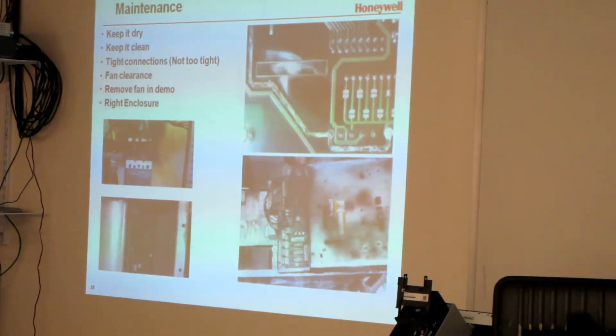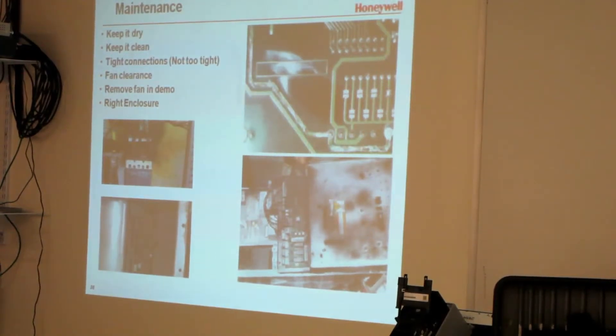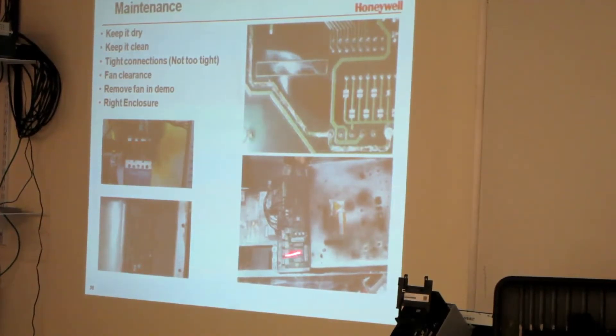So, important things are maintenance. Keep it dry, keep it clean, tight connections. One of the biggest problems you have is people over-tighten the connections and they break. These don't just plug in, they have to be soldered in place. And I want to be able to show you how to remove the fan on the newer model. I'm going to do that. In the right enclosure, you want to make sure that you have the proper enclosure. You can see some spots here where you've got dirt or moisture on the boards. And that kind of does a number on the circuit. Have you ever heard one of these things go pop?